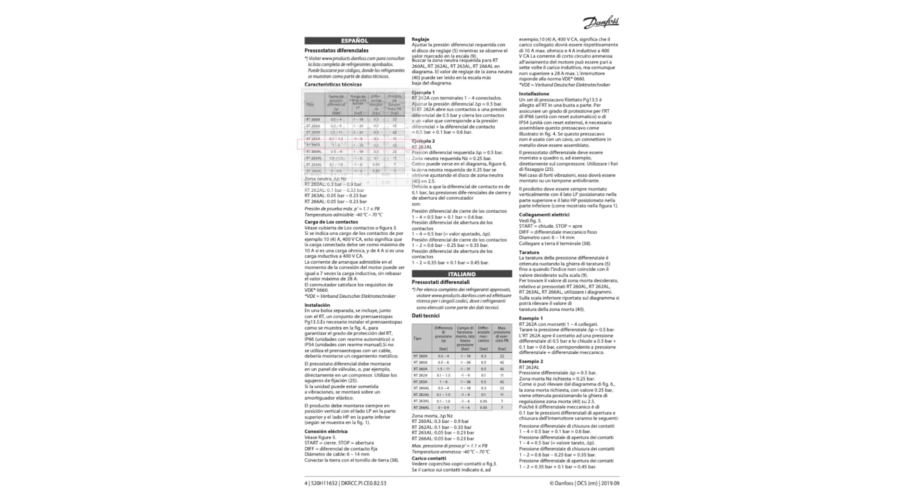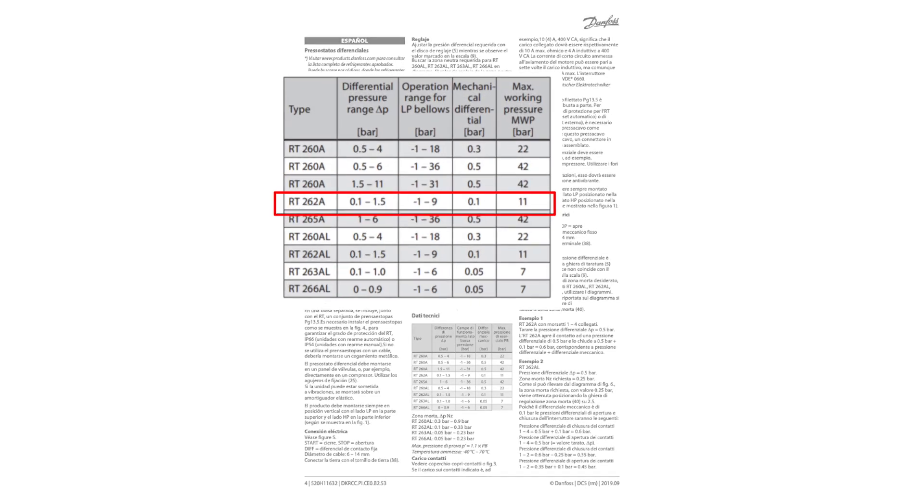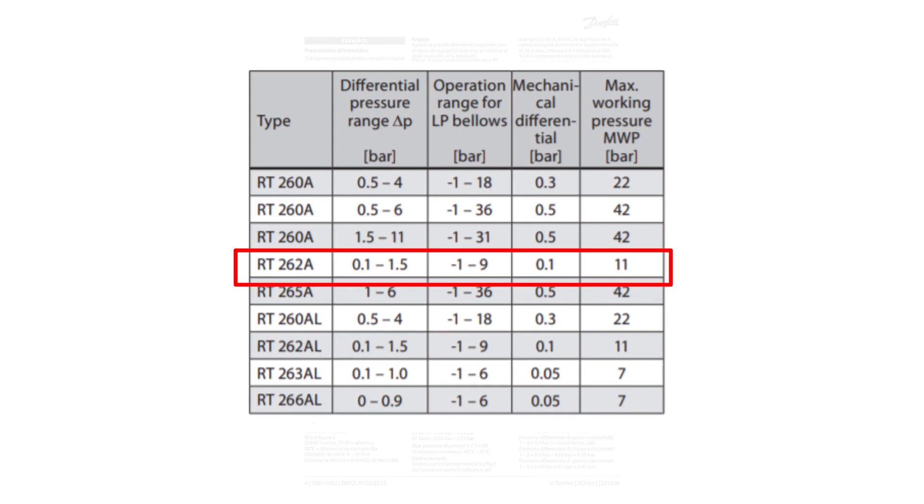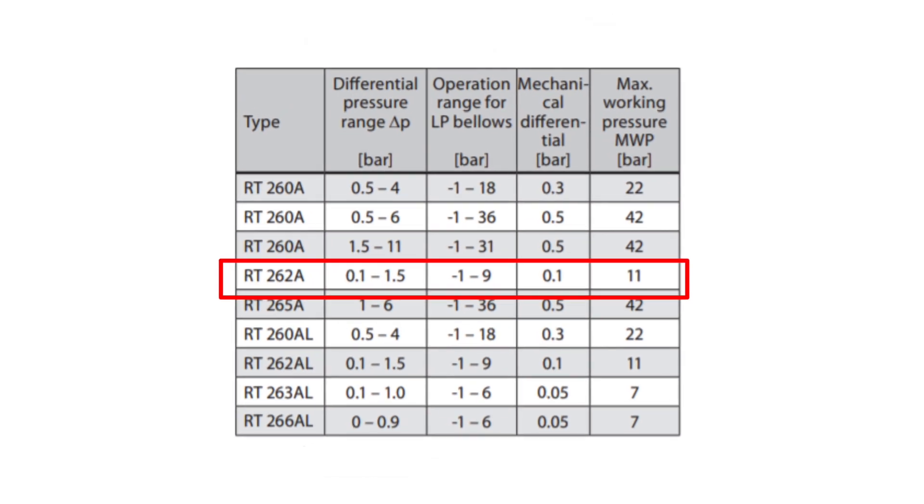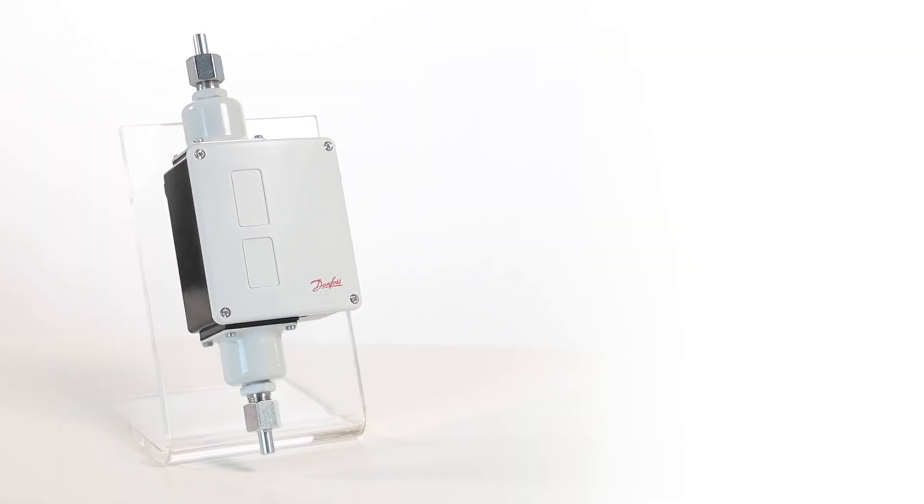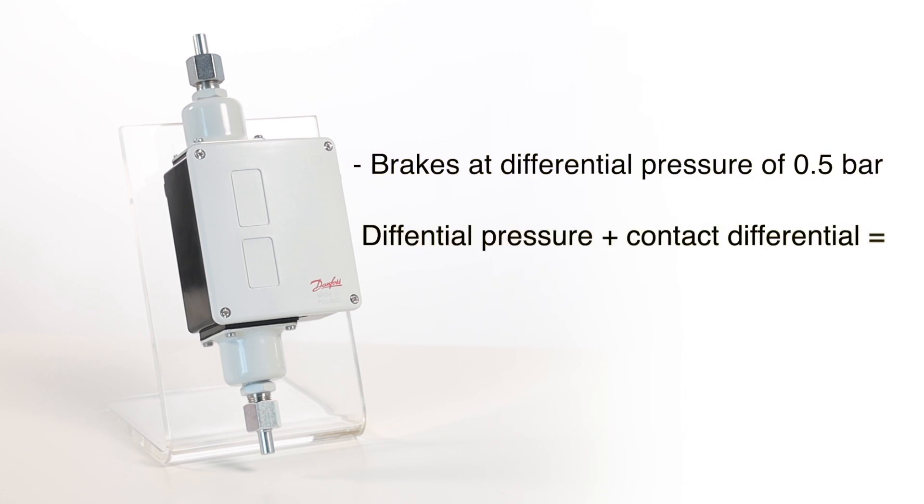In the instructions, you will find the table where you can read which mechanical differential level corresponds to the required levels needed. The RT262A breaks at a differential pressure of 0.5 bar and makes a differential pressure plus contact differential equal 0.5 bar plus 0.1 bar equaling 0.6 bar.